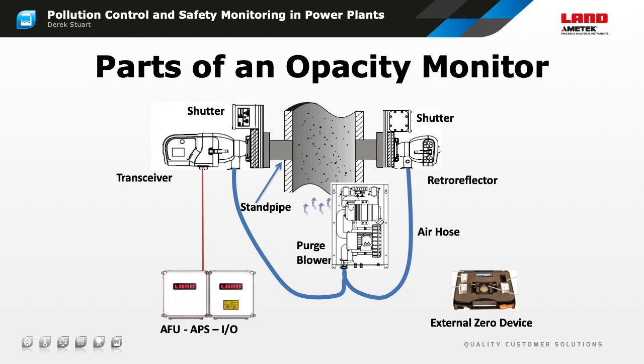The AFU APS-IO is an interface box which includes a mains power supply, drivers for the shutters and other accessories, as well as additional inputs, outputs, and screw terminal connections for user terminations. Finally, the external zero device is used to simulate a clear stack condition for calibration and testing. For applications subject to US EPA rules, it is required for the quarterly calibration audit.